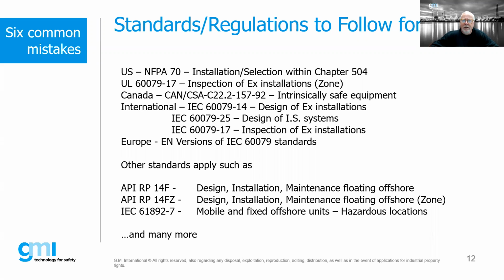On the international side of things, we have a couple different IEC standards in the 60079 series that we follow. The -14 is a great standard to get your hands on and be familiar with. The -14 standard is very much the basis for a lot of the competency programs. So if you really want to understand programs like CompEx or the IECEx CoPC program, the -14 is pretty much the benchmark we use for training and assessment. There is some information on design of EX installations as well as IS included in there. The -25 standard is the design of a complete IS system. So now we're talking about taking all of the components that you might find in an intrinsically safe system and putting them together. The -17 is our inspection of EX installations, which include IS. And of course, in Europe, we take the EN versions of the 60079 standards and apply those.